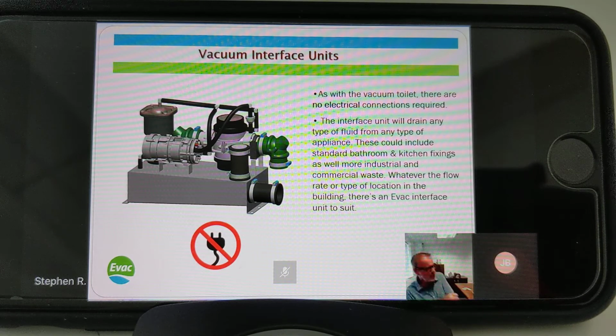The interface unit, like the vacuum toilets, again, requires no electrical power to operate. And it's not always one sanitary appliance to one interface unit. The picture you're seeing on the screen there was taken in a cinema toilet area, and there are 6 basins there, one's just slightly out of shot. All of those basins drain down to one interface unit that was positioned behind one of the panels in front of the wash basin, with the riser going up to high level inside that orange void there. So if you had a run of 6 basins going to one interface unit, but if you had 2 basins on opposite sides of the room, then you may need 2 interface units. So it's all about flow rate rather than number of items.